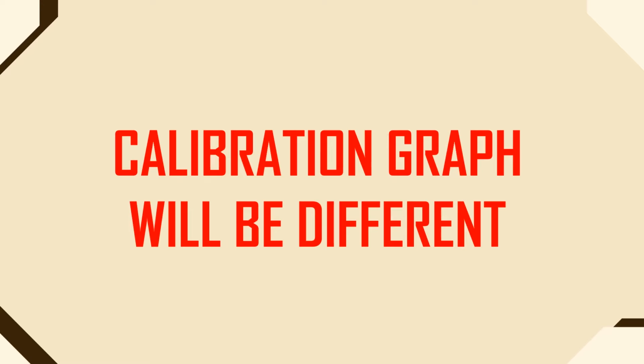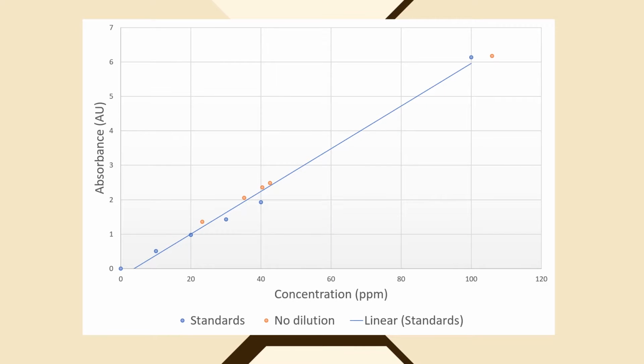The answer is the calibration graph will be different. To answer this question, let's look at the calibration graph along with no dilution samples plotted. The reported linear concentration range is 0 to 100 ppm, and the average concentration of caffeine from the samples without dilution lies within the line between 23 to 105 ppm.